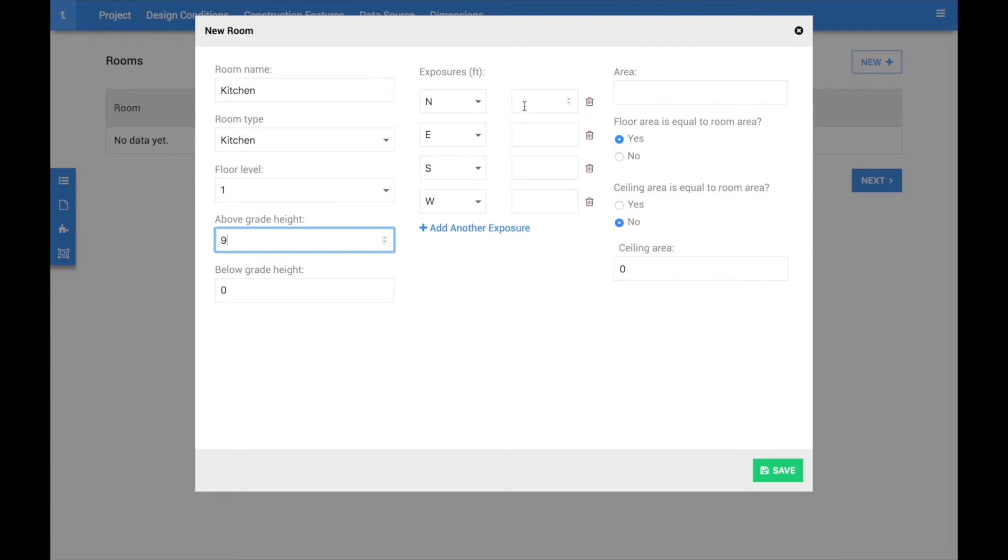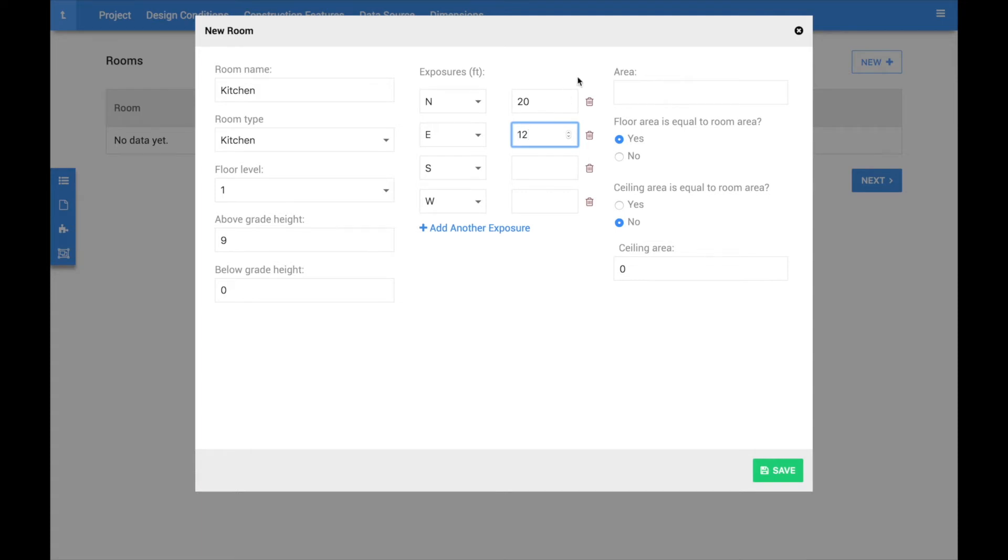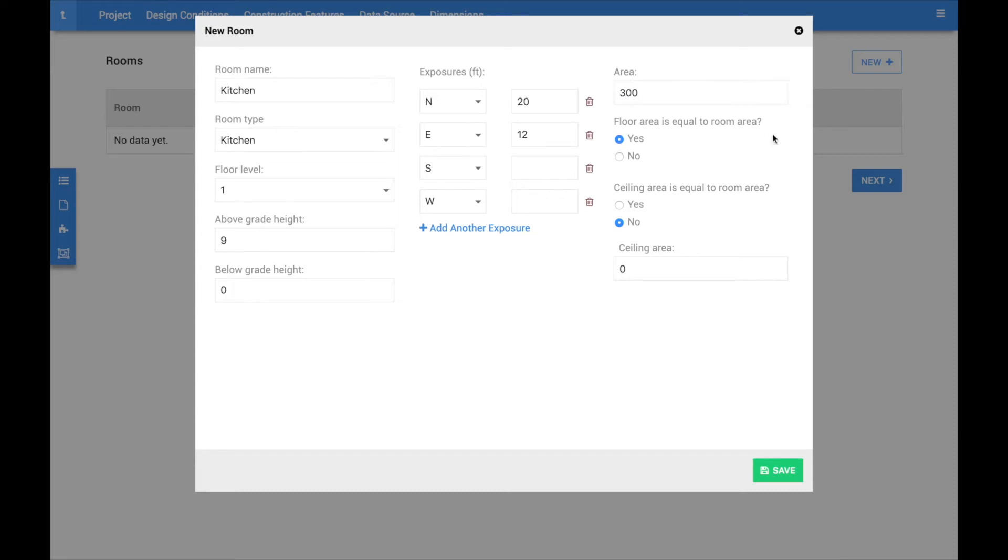From there, you need to specify the dimensions of the room. Enter the total linear feet of outside walls that face each exposure. If you enter at least two exposures, CoolCalc will automatically attempt to calculate the area of the room. However, you can easily override this value if the room is not a perfect rectangle. If the room is internal to the house and does not have any outside walls, then simply leave the exposures blank and manually enter the area of the room.